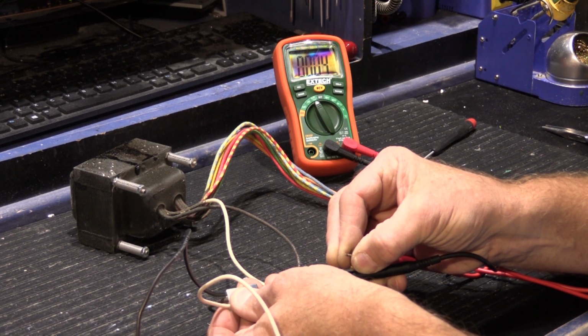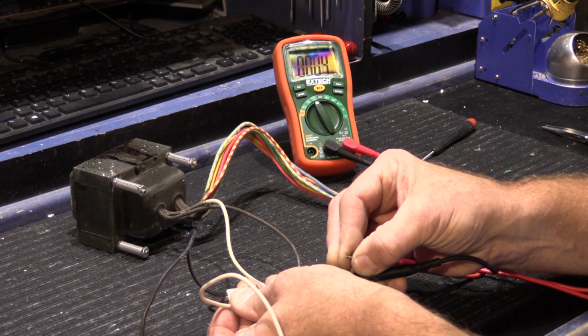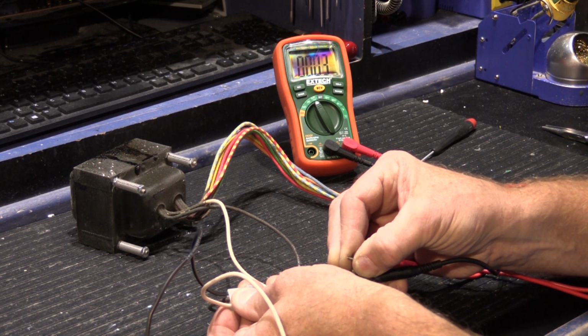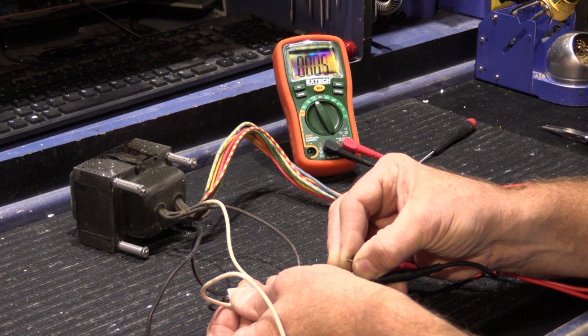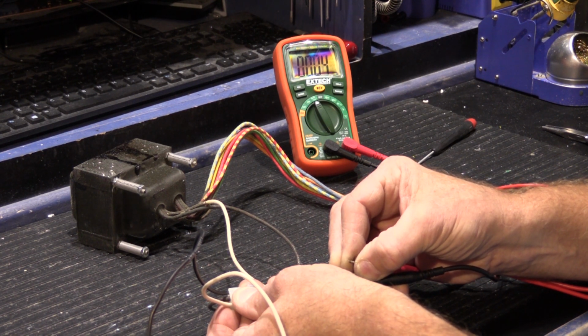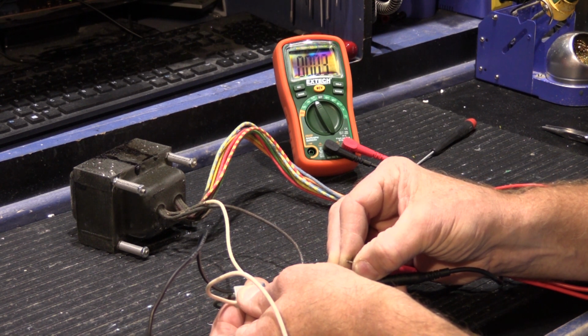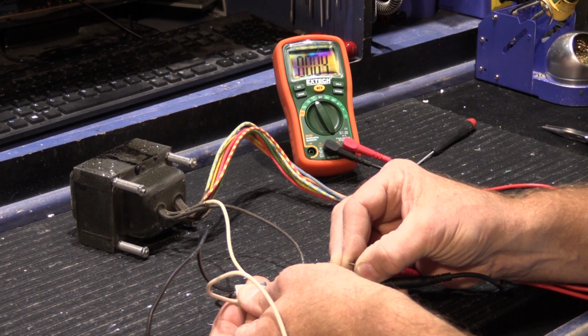You may think the difference between 3 and a half isn't that far apart, but it is on a transformer, so it could be that the winding is shorted. What could happen is if there's a failure in the enamel insulation on the windings, that would cause it to short out.